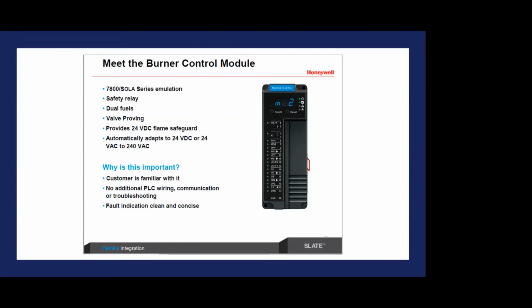So the unique thing about this burner control module - we talked about the 7800 and how it's configurable. One of the first things we have to do is figure out what functionality we need, and that's how we pick a model. Whether that's something as simple as a flame relay, an RM7823, maybe a semi-automatic RM7838, or a natural draft 7890, 7895, and so on - every one of those models brings with it functionality as we move across that product platform.